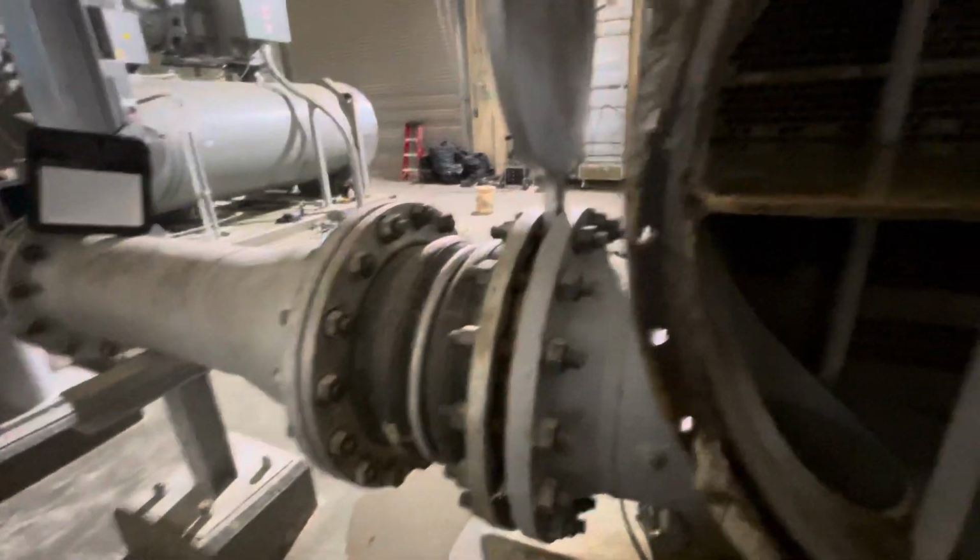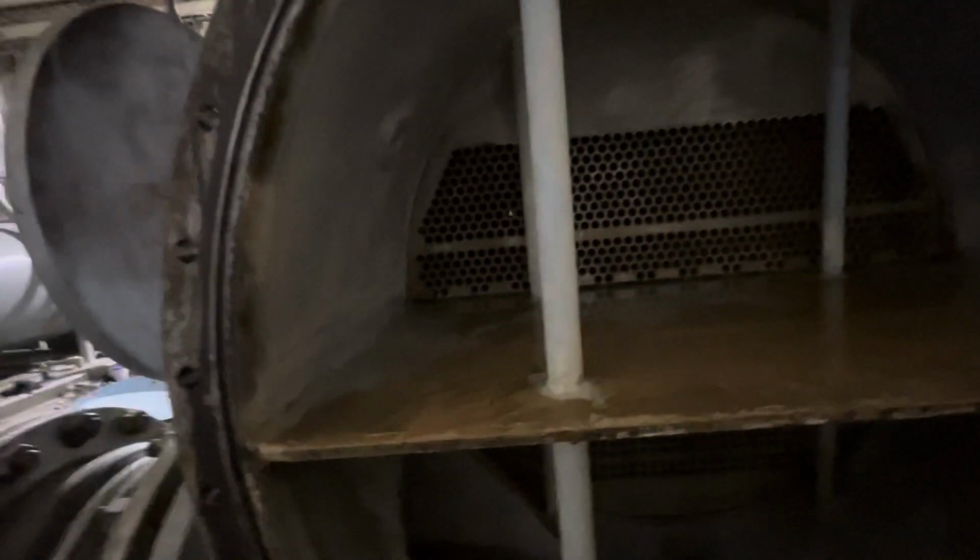Now inside the tube there is water, condenser water, which is used for cooling the freon. And outside the tube in the shell there is refrigerant R134A, which is environmentally friendly. So the cool condenser water is coming in at approximately 84, 85, and going out at 95, 94.